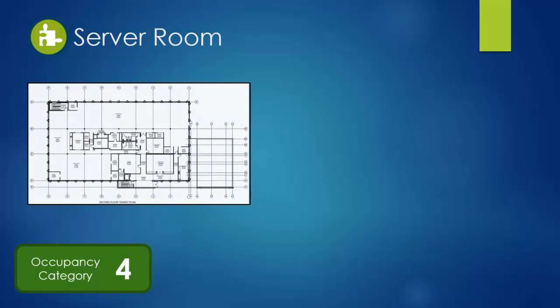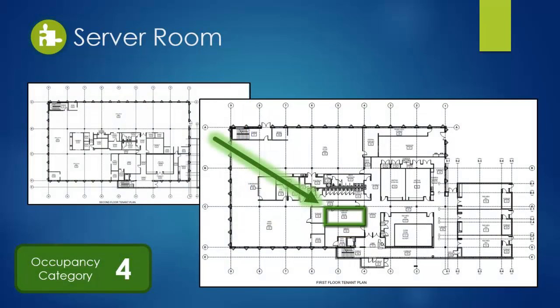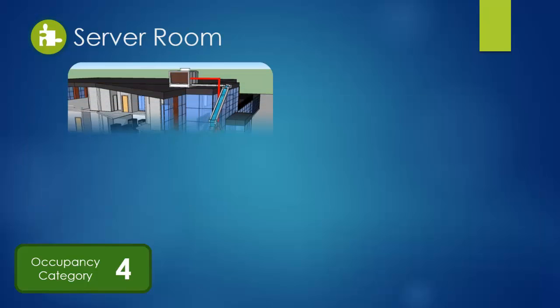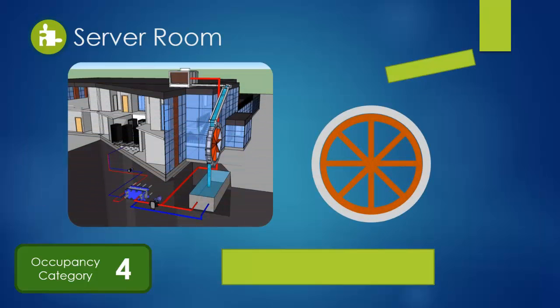Now we will discuss the components of the server room, which makes up occupancy category 4. To condition the load due to the server racks, a water wheel will be used as the primary method for cooling, and a water-to-water heat pump will be used for any additional cooling needed. The water wheel is used to reject heat from the water loop, which cools the server racks throughout the year.